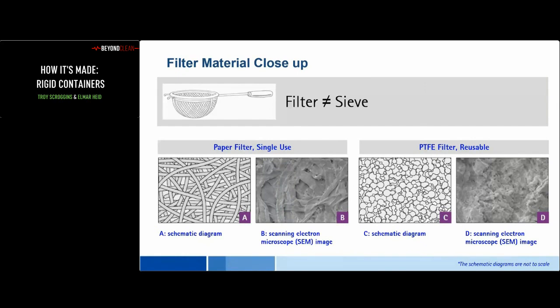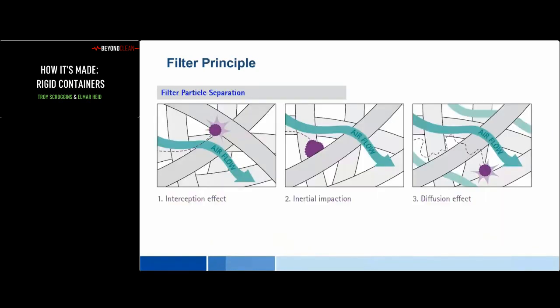Single-use filters are most commonly made of multi-layered overlapping cellulose or polypropylene fibers. The cellulose or polypropylene fibers are intended to be used only once because the material may be fatigued by the sterilization. Reusable filters are made of polytetrafluoroethylene, PTFE, which isn't fatigued by the sterilization and may be reused because they are highly resistant against aging. They are hydrophobic, which means non-wetting, show a high density, and are resistant to high temperatures. These images show a diagram and electron microscope view of paper and PTFE filters. Note how they create a complex, tight pattern. In containers, these filters are held in place securely with retention plates.